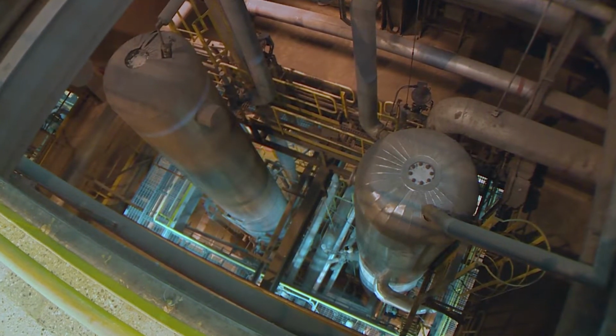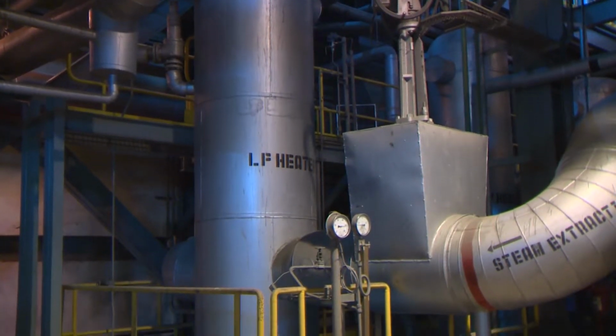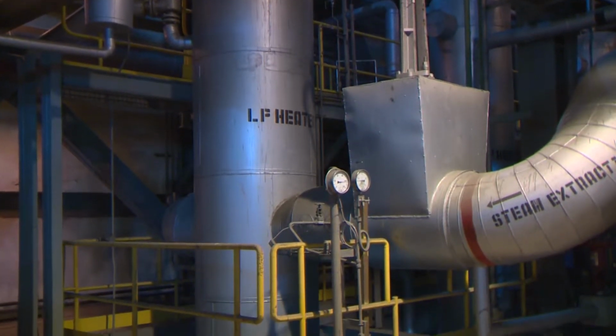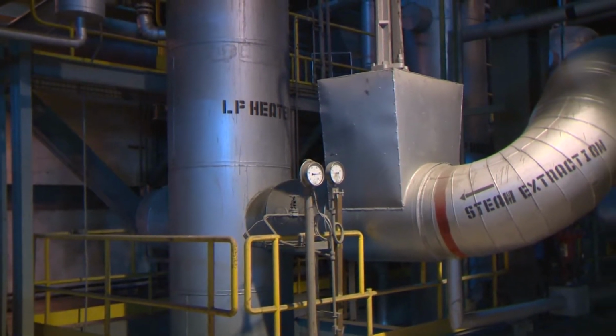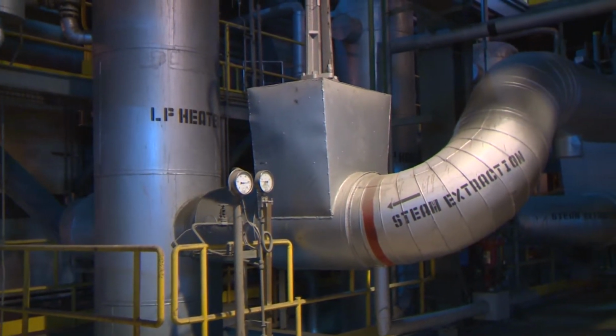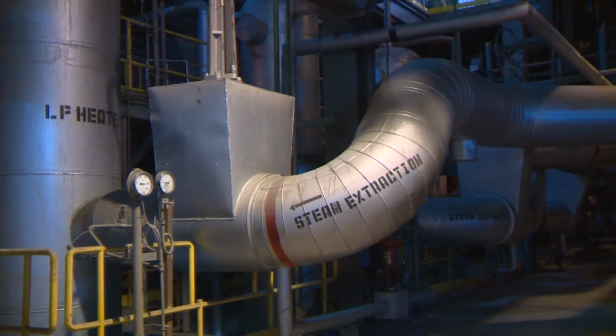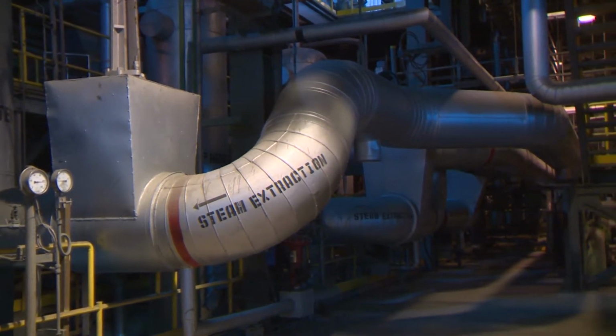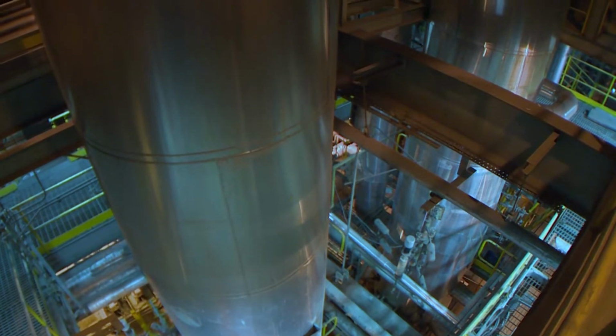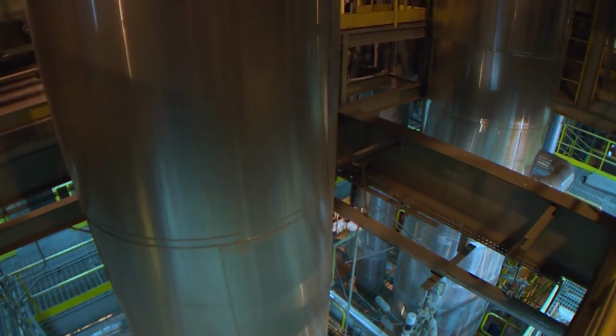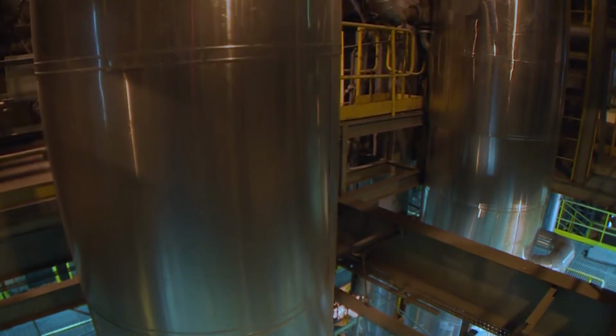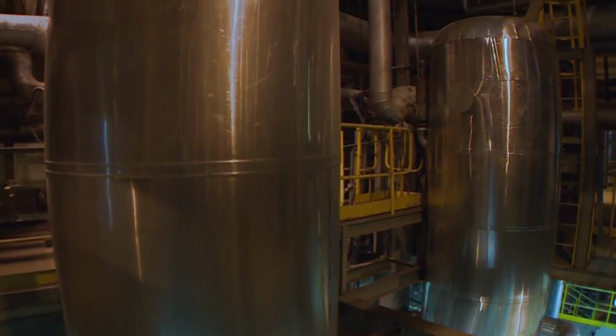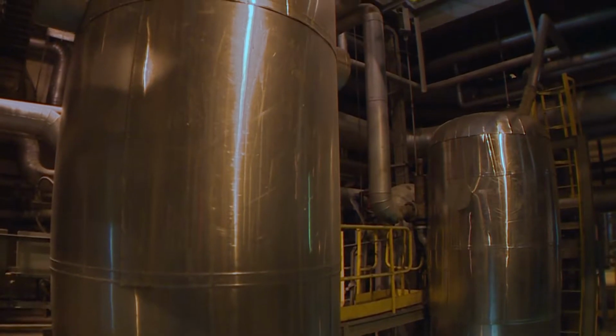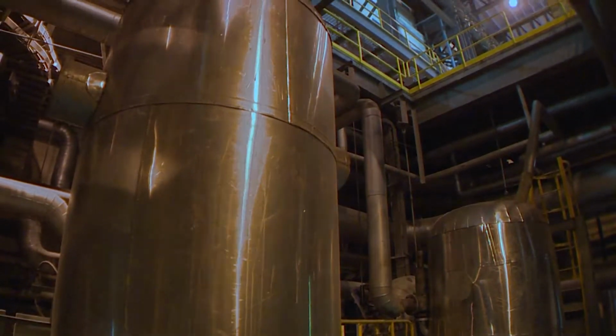Regenerative feed water heating system. The low pressure and high pressure heaters are used to increase the feed water temperature by the extraction steam from LP, IP turbines and cold reheat line. Both heaters are vertical type. The drain condensate of the LP heater is cascaded to the hot well through a drain cooler and flash box. The drain condensate from the HP heater is sent to the deaerator.